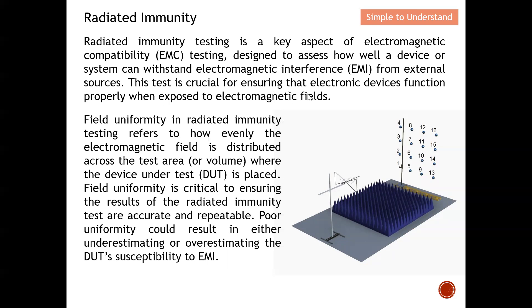This test is critical to ensure that electronic devices function properly when exposed to real-world electromagnetic fields. Field uniformity in radiated immunity testing refers to how evenly the electromagnetic field is distributed across the test area where the DUT is placed. As shown in this diagram, this is a four-by-four grid — 16 points in total — which is the test area where you place your DUT. We need to ensure these 16 points are evenly distributed, with a maximum difference of only ±6 dB.